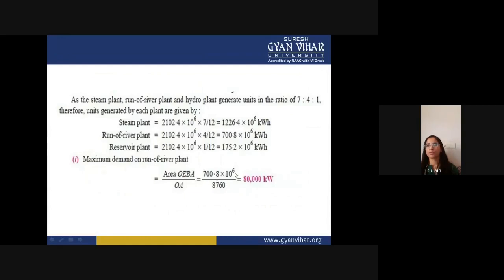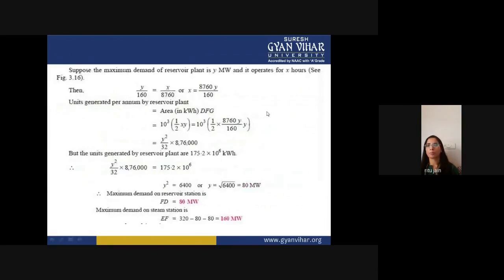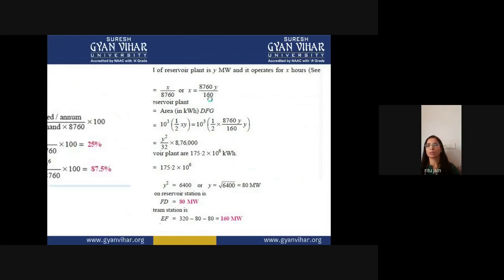So 700.8 into 10 to the power 6 kilowatt hour units are generated by the runoff river plant. When you divide it by the total hours in a year, then you will get the maximum demand on the runoff river plant. Now, suppose the maximum demand of the reservoir plant is Y megawatt and it operates for X hours, then you can write Y upon 160 is equal to X upon total hours in a year, and X is equal to 8760 Y upon 160.